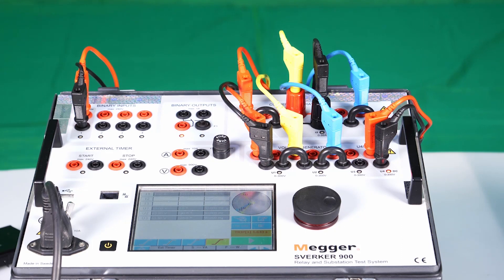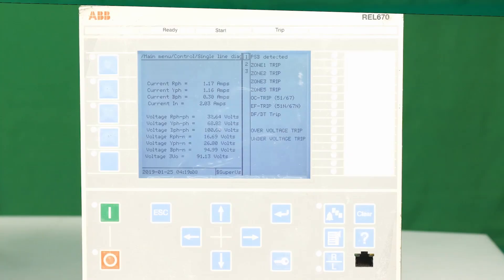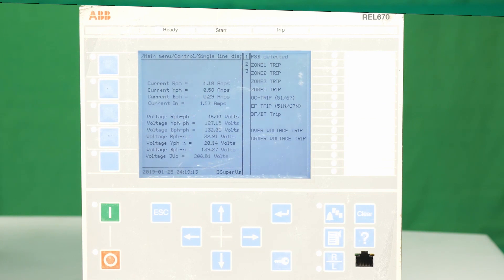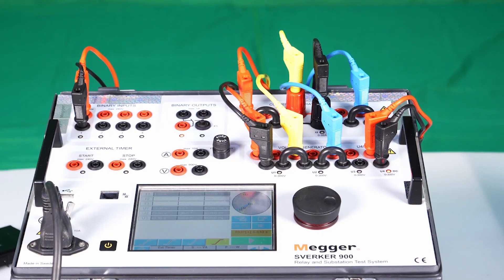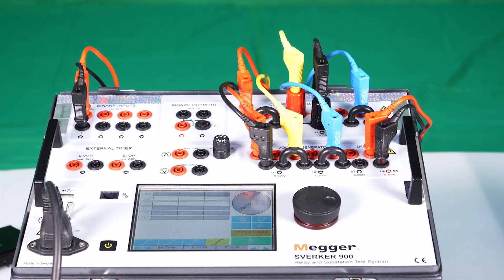This is a Neutral Directional Overcurrent application example using the Ramping Screen. An ABB REL670 relay is configured for Neutral Directional Overcurrent with a setting of 0.2 Amps and RCA 55 degrees. The MTA is calculated as 360 minus RCA, which is 305 degrees. The operating region is MTA plus or minus 85 degrees, giving a range of 30 degrees to 220 degrees.